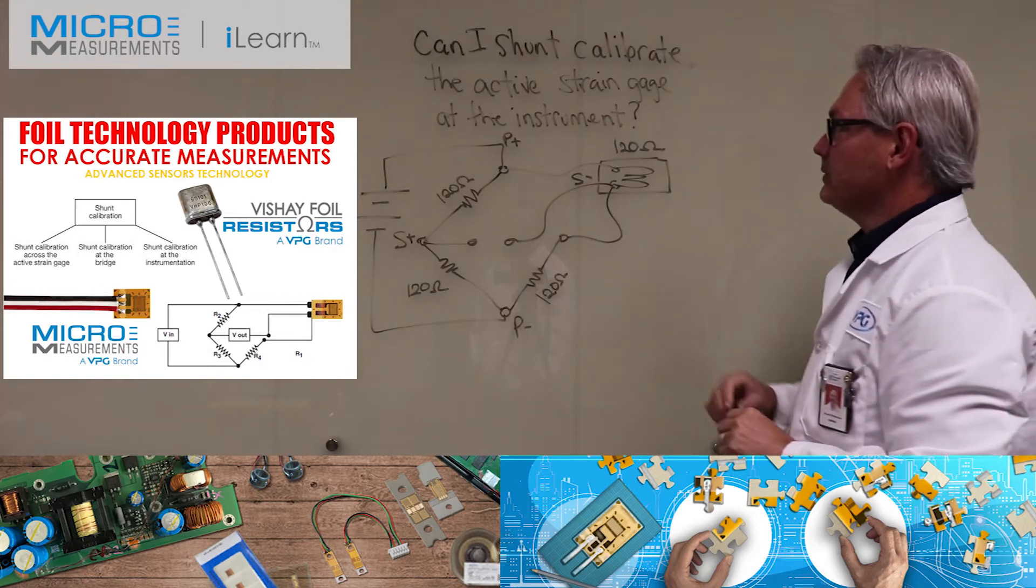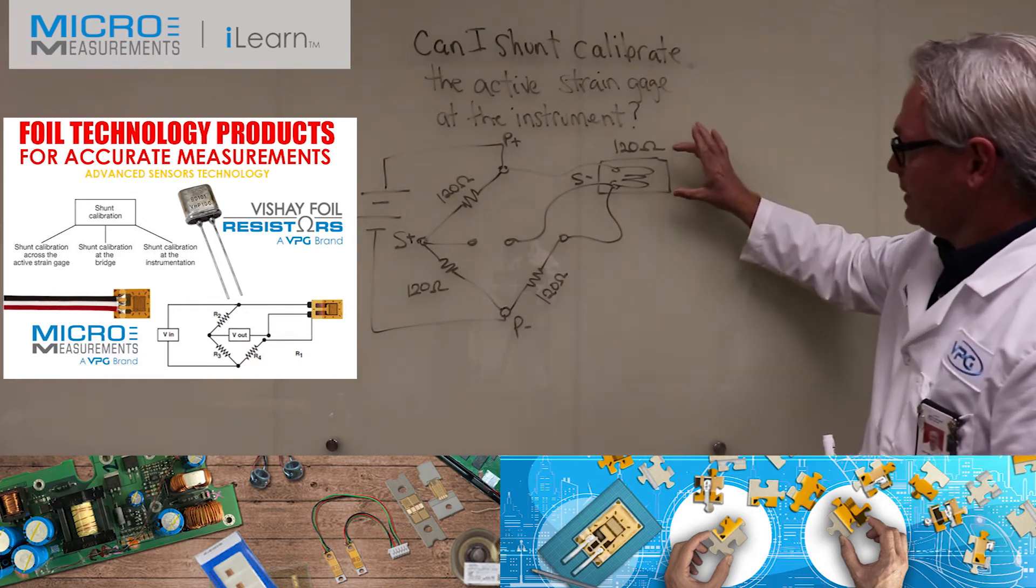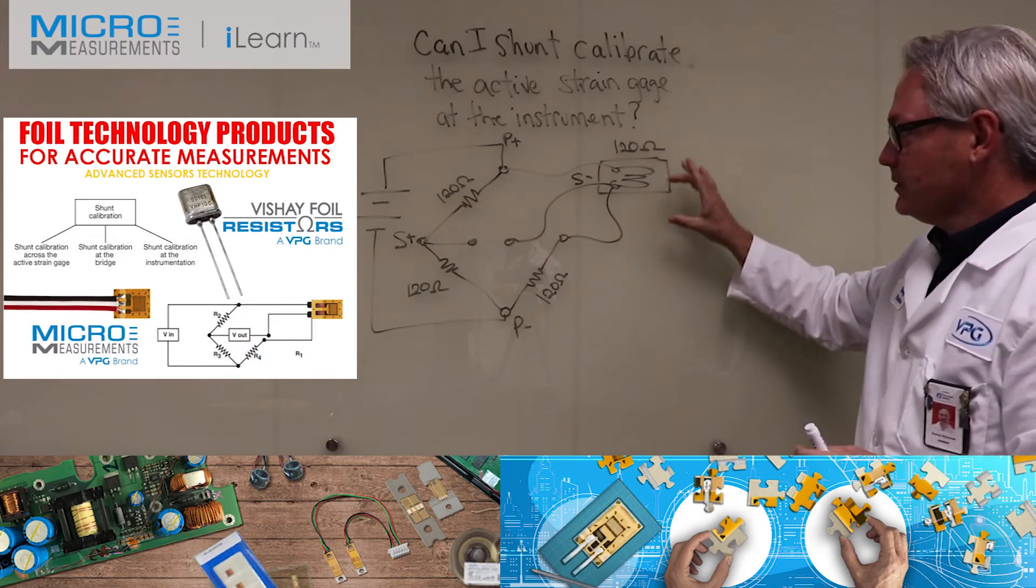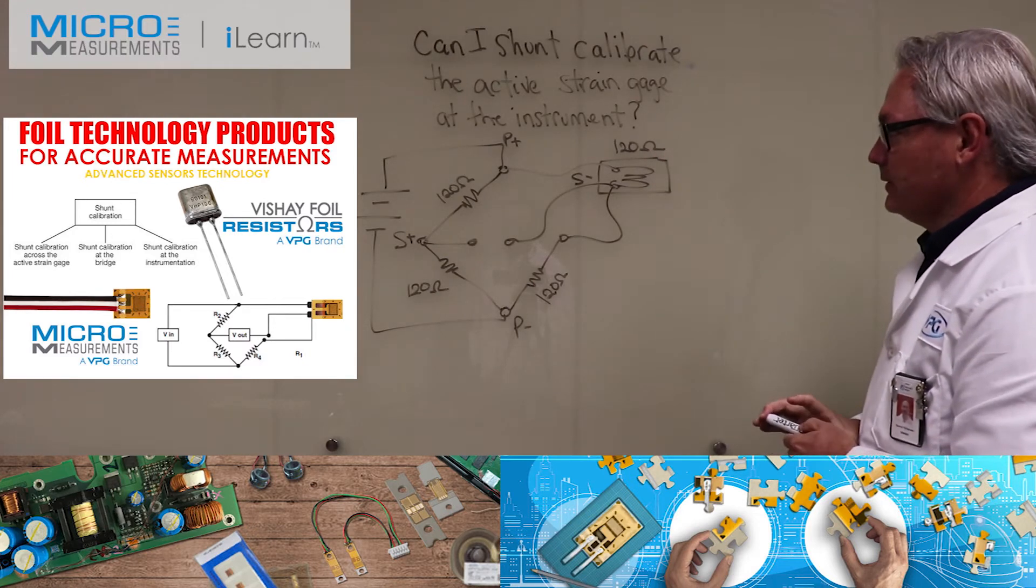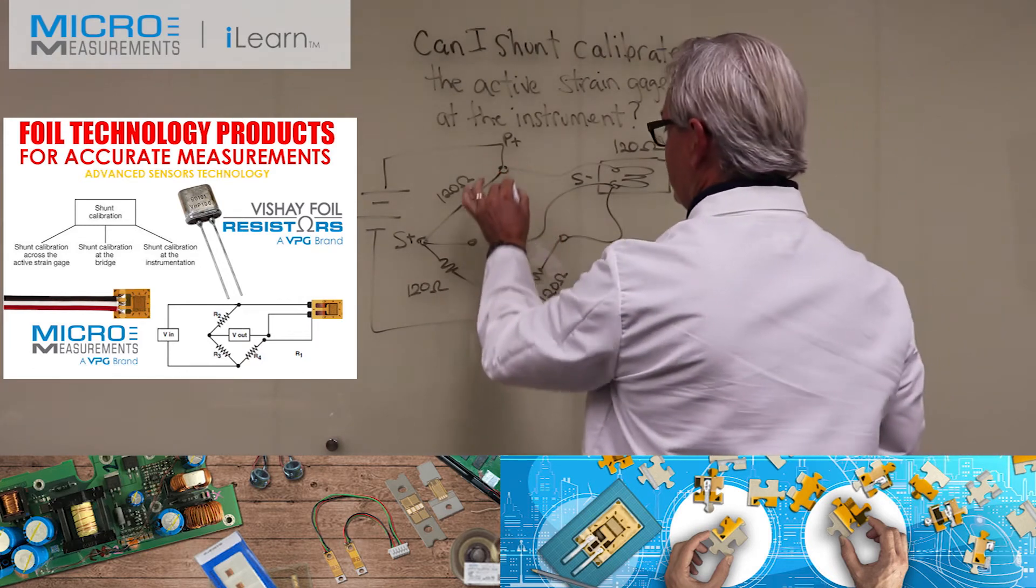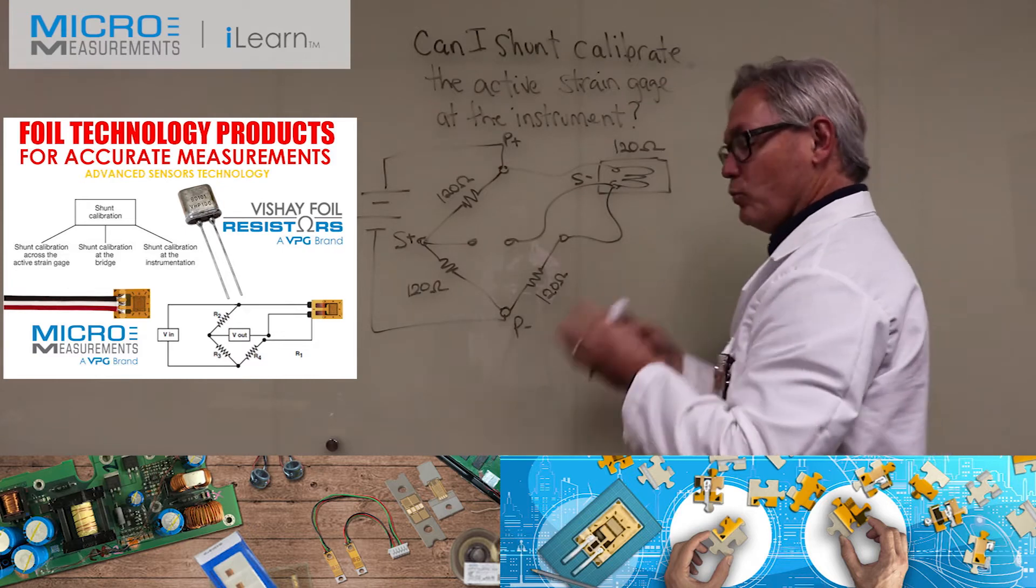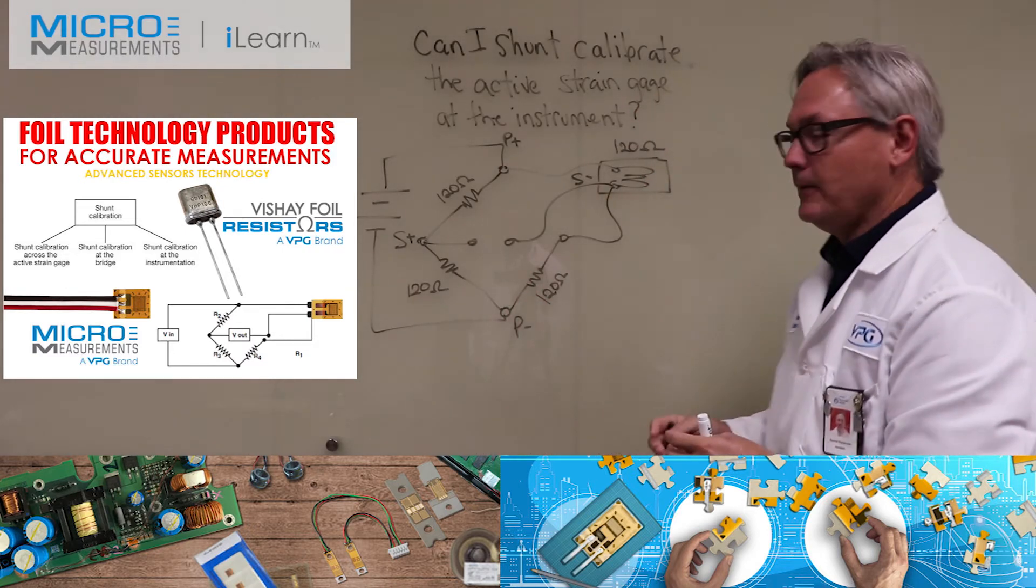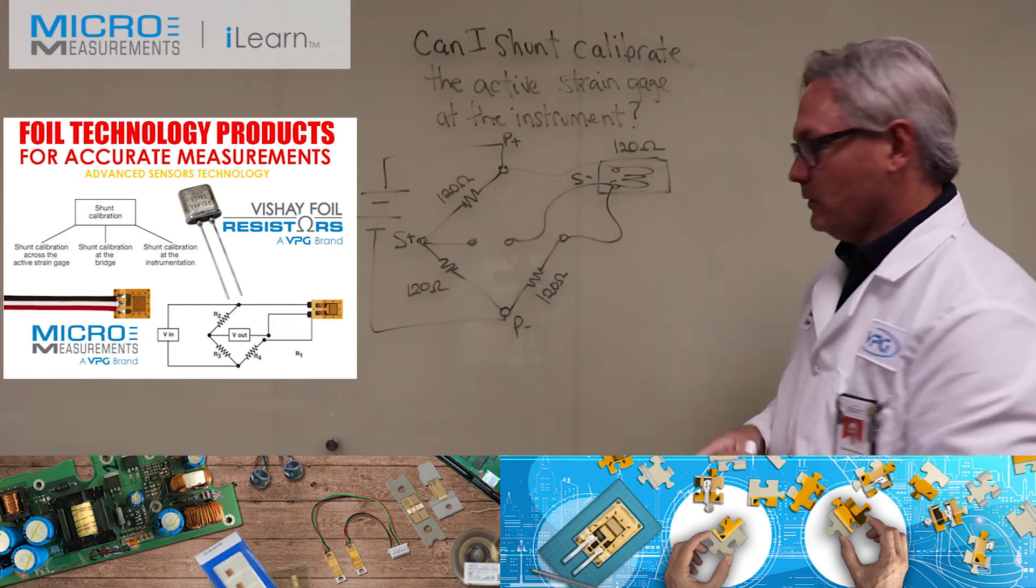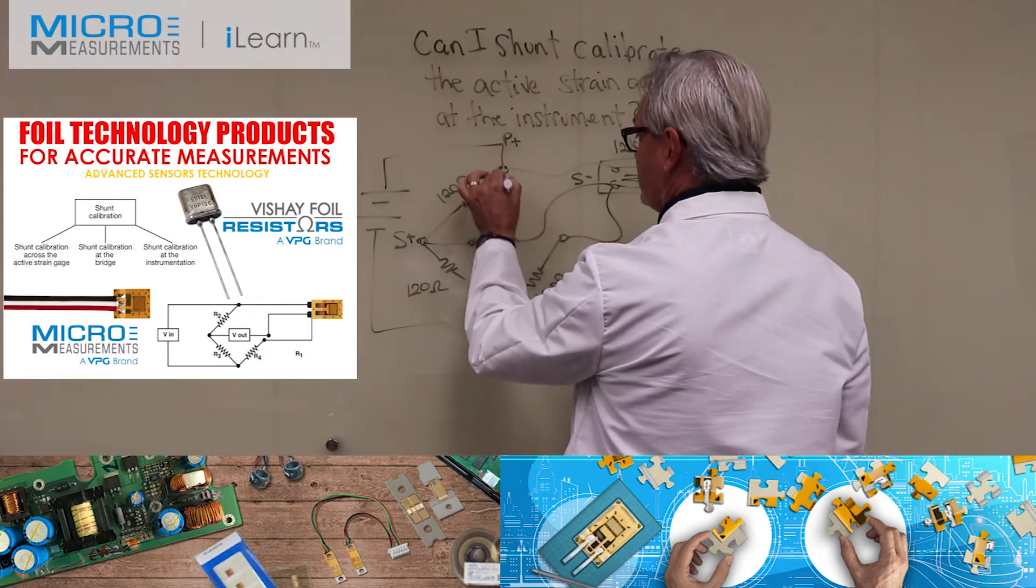When we talk about "can I shunt calibrate the active gauge at the instrument," we're talking about connecting a resistor in parallel across the strain gauge, which is not a very convenient location out at the gauge. But imagine doing this back over here at the instrument where it's much more convenient. Can you shunt calibrate this strain gauge back over at that location? One of the most obvious spots to do that is right here.